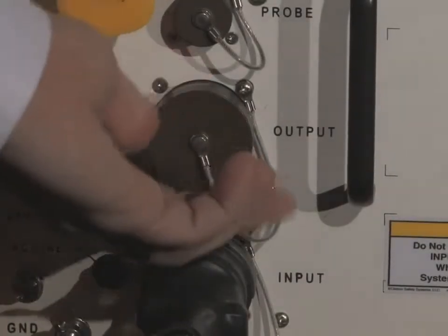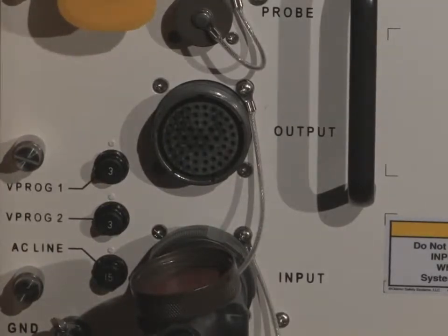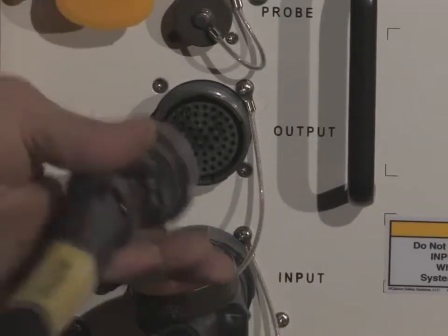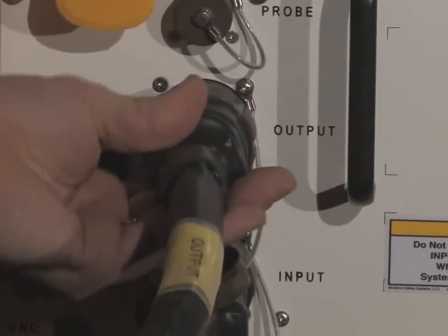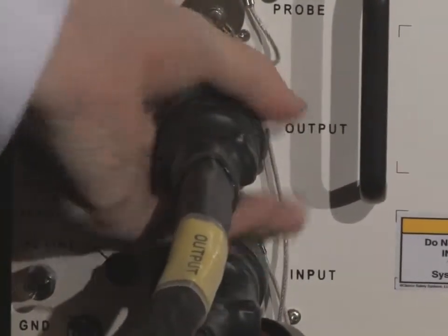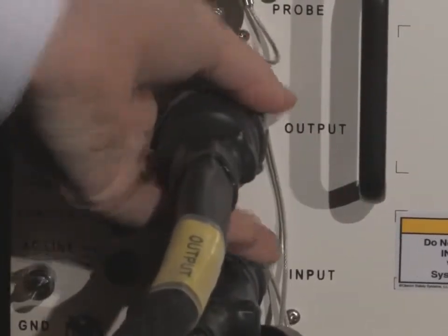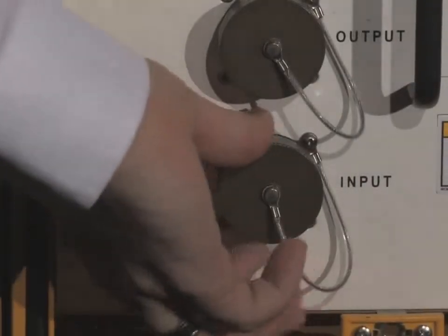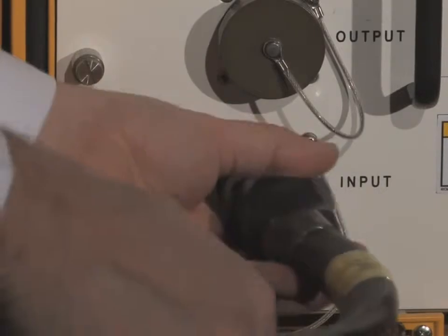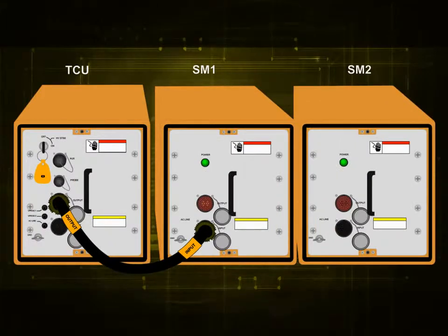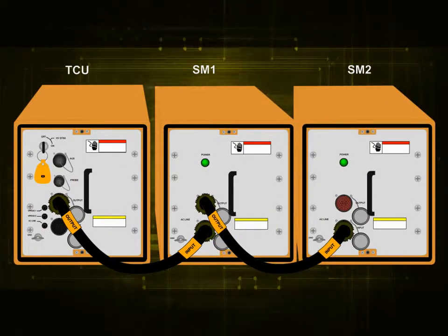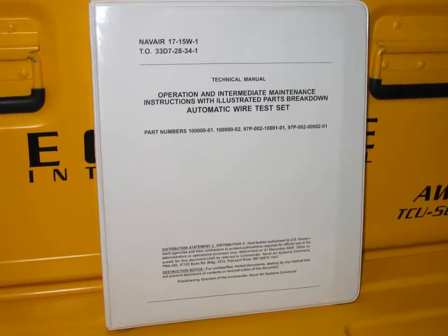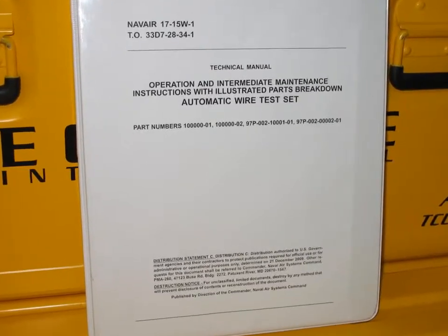To connect a switch module, locate the umbilical cable and unfasten the output dust cap on the rear of the test control unit. Connect the output end of the umbilical cable to the output connector located on the rear of the test control unit. Unfasten the input dust cap on the rear panel of the switch module and attach the umbilical cable end marked input to the switch module input connector. If additional switch modules are needed, connect output to input to form a daisy chain between each switch module. To ensure proper configuration, please refer to the Joint Services Technical Manual for proper addition of switch modules.